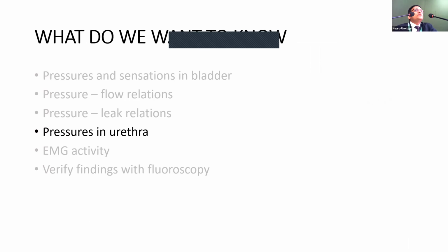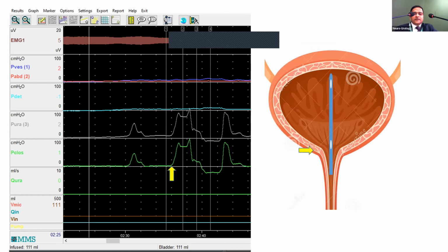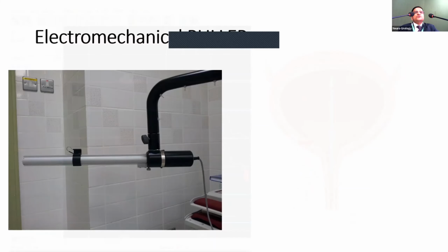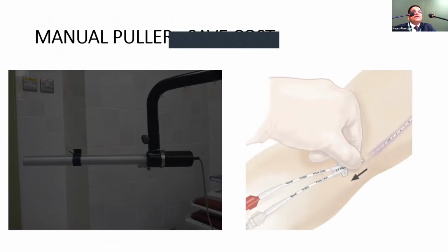If you're a person doing urethral pressure profilometry also, you need an additional lumen catheter, like a triple lumen catheter. There, it is difficult to save cost. The only way is you re-sterilize properly. We do re-sterilize using LTSF or plasma, whichever is available, after proper mechanical cleaning, and these go on and on without causing any problem. And you can use a puller, whether it's an electromechanical puller, or you can use your own hands at 1 centimeter pulling. You can add more dots to these UPP catheters.